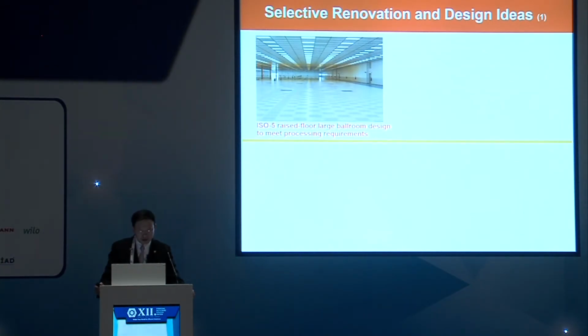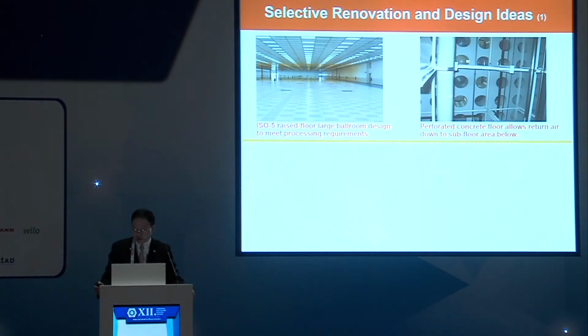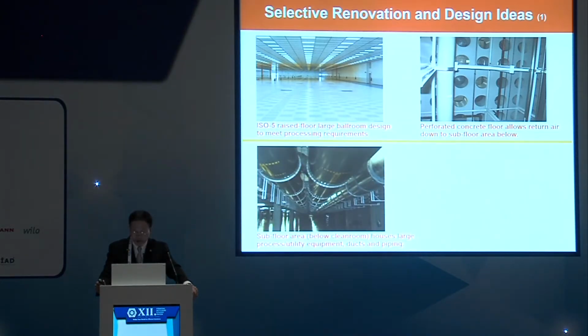Some other renovation design ideas. And this is the ISO 5 raised floor, large ballroom. And this is the photo underneath these perforated floor panels. If you stand in the room below this floor, you will see a lot of circular openings. This allows the return air to go down from the clean room space to the subspace. So this uses very heavy concrete panels, poured concrete. And this is also at the basement level, huge ductwork made of stainless steel, to move the air.